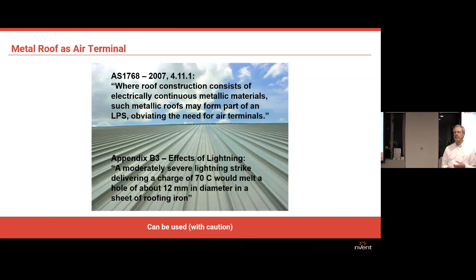And in the appendix at the end of the standard, it gives you an example of what will happen if your roof is struck. A moderately severe lightning strike delivering a charge of 70 C would melt a hole of about 12 millimeters in diameter in a sheet of roofing iron, but they're not particularly specific. Well, they don't say at all how thick their roofing iron is, so it's just an indication, which is why IEC 62305 is a better reference.